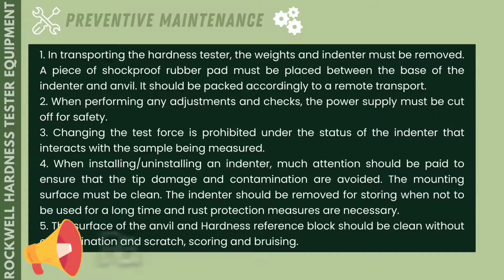Next is the preventive maintenance for the Rockwell hardness tester. Number 1. In transporting the hardness tester, the weights and indenter must be removed. A piece of shockproof rubber pad must be placed between the base of the indenter and anvil. It should be packed accordingly for remote transport. Number 2. When performing any adjustment and checks, the power supply must be cut off for safety. Number 3. Changing the test force is prohibited while the indenter is in contact with the sample being measured.